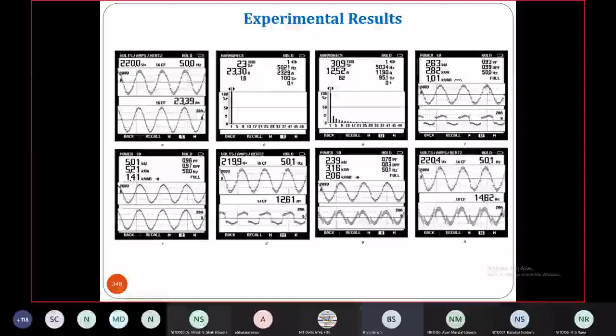Another system we took up combines hydro and solar. For the uncontrolled hydro, we use a synchronous reluctance generator, which is more efficient than an induction motor, along with a capacitor, and the converter takes care of voltage and frequency control. Extra power goes to the battery, and if load increases, power comes not only from solar but also from the battery to feed the load. So we have hydro, maybe canal-top, and solar also on canal-top, and this system can feed a variety of local loads in a standalone setup.